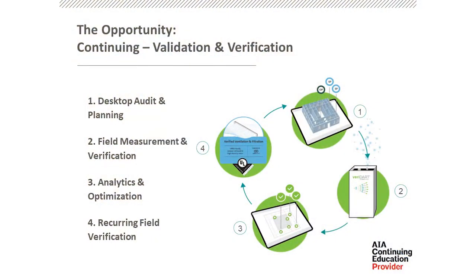The process, at a high level, starts with a desktop audit. Based on the building design and operations, how should a building be performing? We use things like ASHRAE's equivalent air change calculator to get a quick read on where we think the building is performing. But importantly, we know design does not equal performance, so we want to go and test against that.